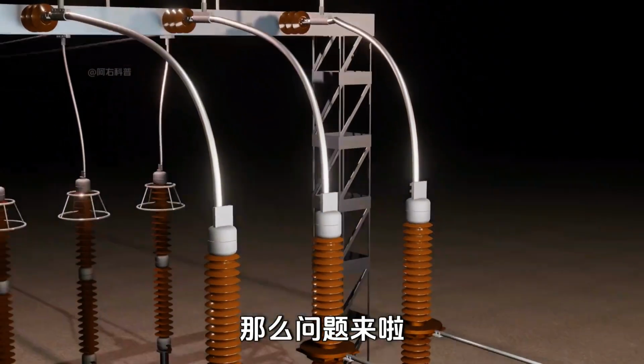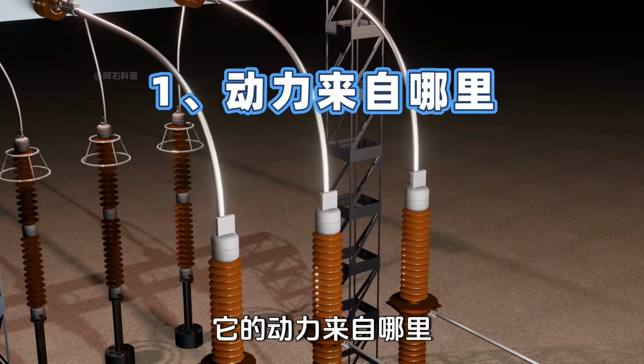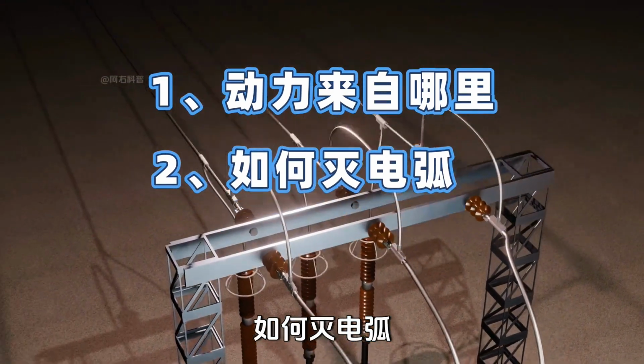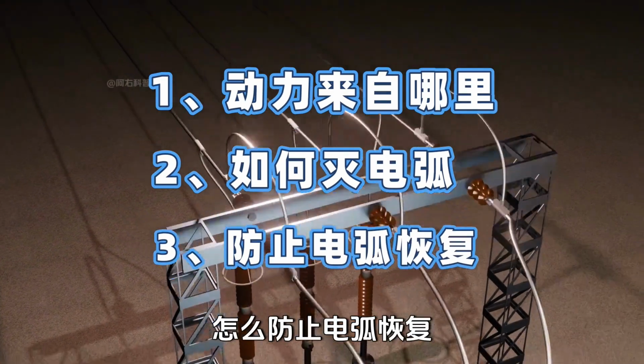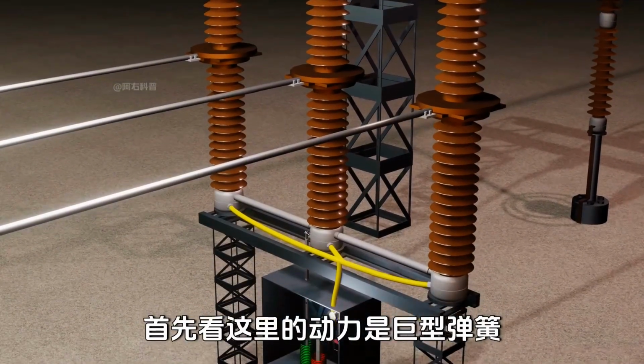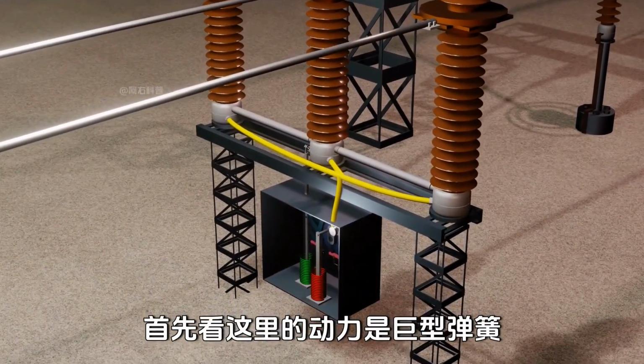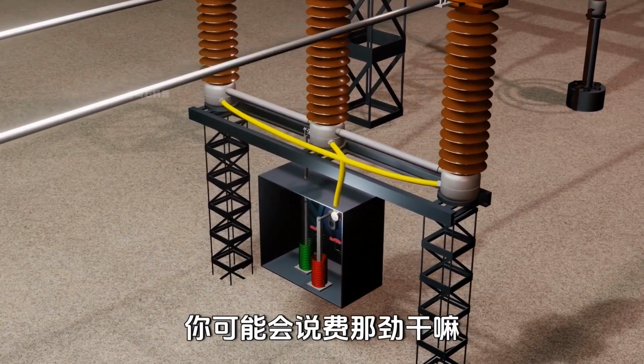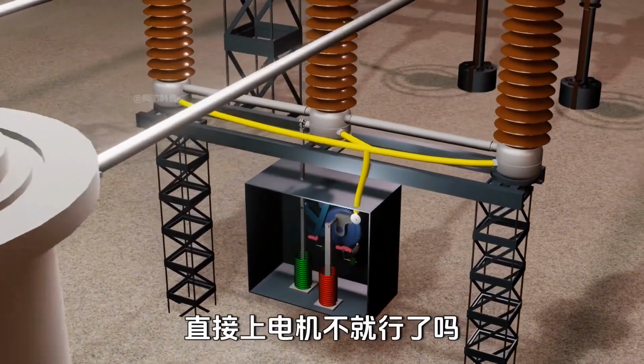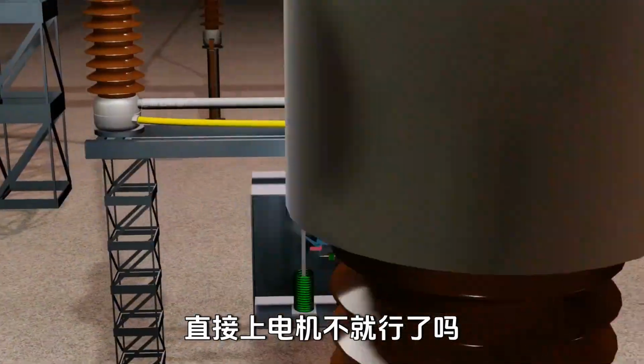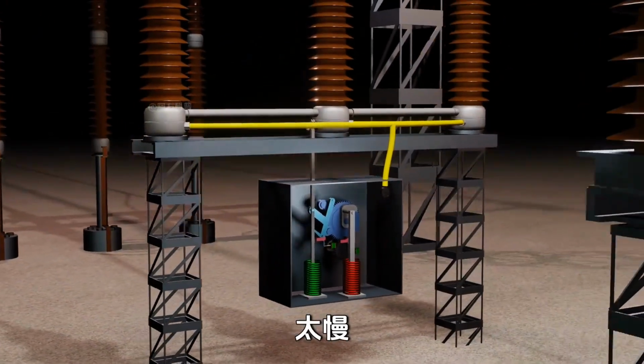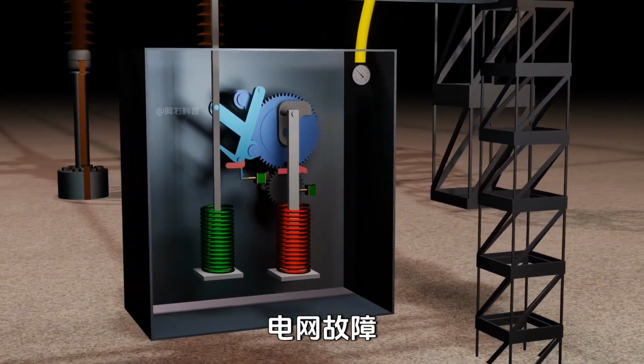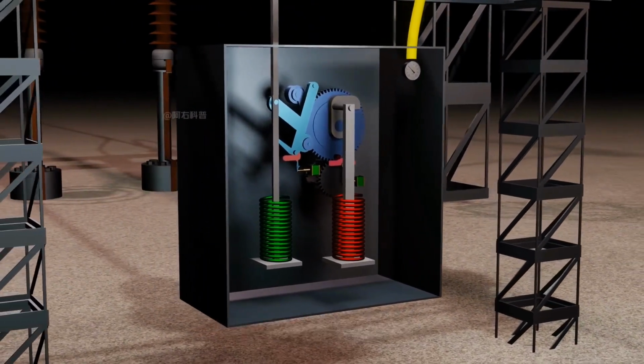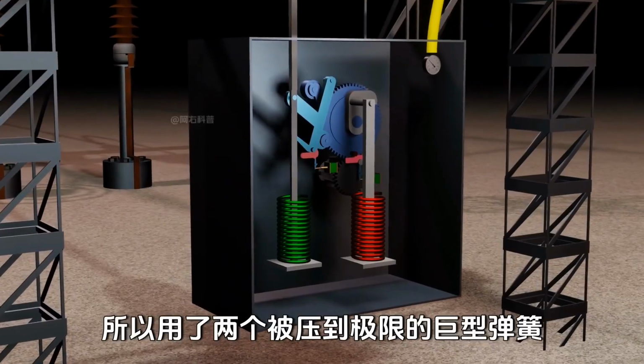Now you might wonder, where does it get its power from? How does it extinguish the spark? And how does it stop the spark from coming back? First, its power comes from a massive spring. You might think, why all that effort? Why not just use a motor? Because that won't work. A motor is way too slow. When there's a fault in the power grid, time is measured in milliseconds, and motors simply can't react that fast.